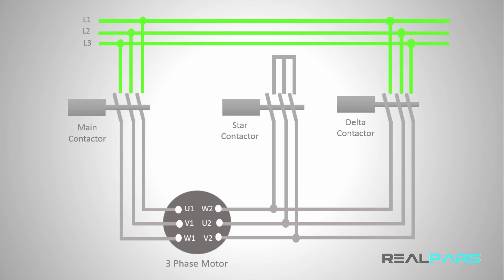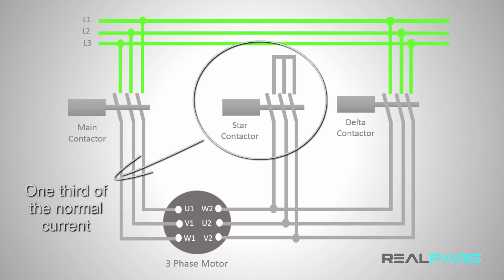One of the common ways to do this is to use a Star Delta Starter for your electrical motor. To do this, you first start the motor in a star connection, and after a few minutes, you'll change the connection to a delta. When you start in the star connection, the current that the motor draws is one-third of the rated current for that motor.